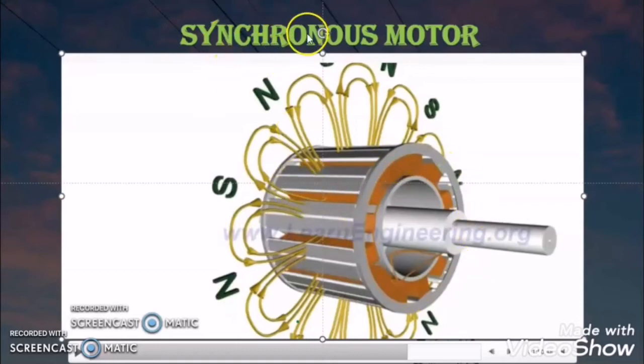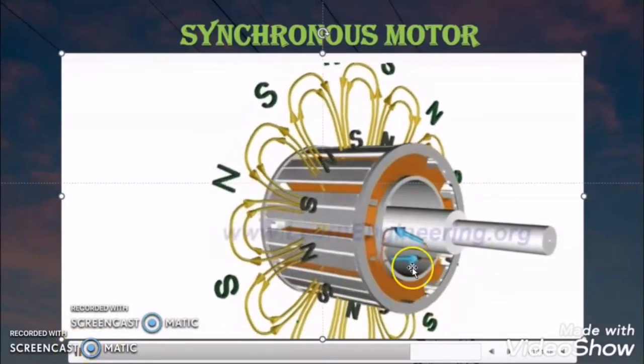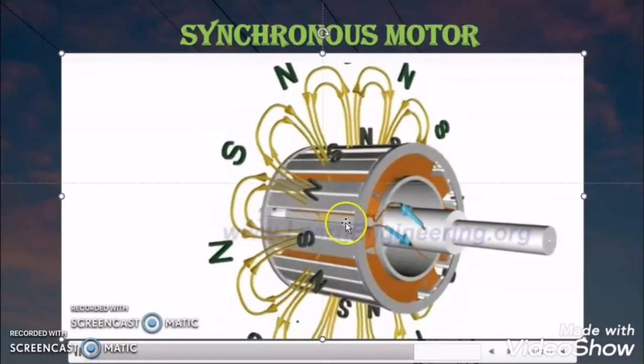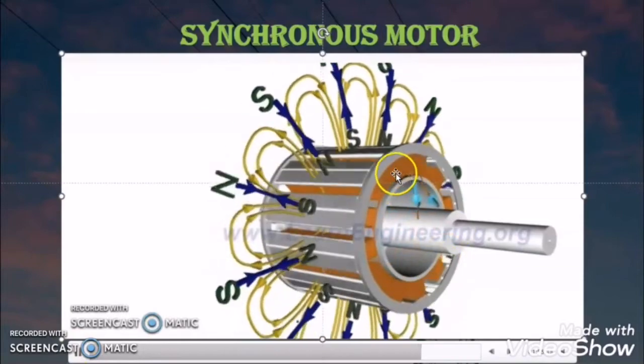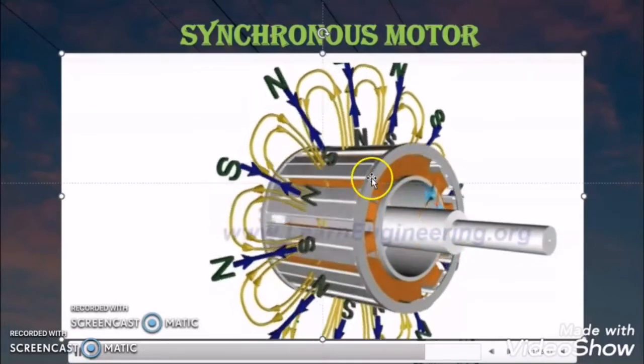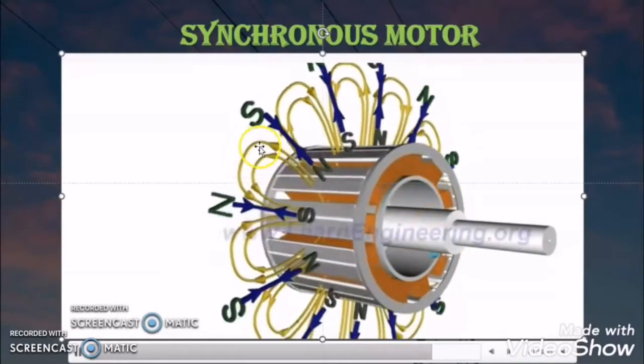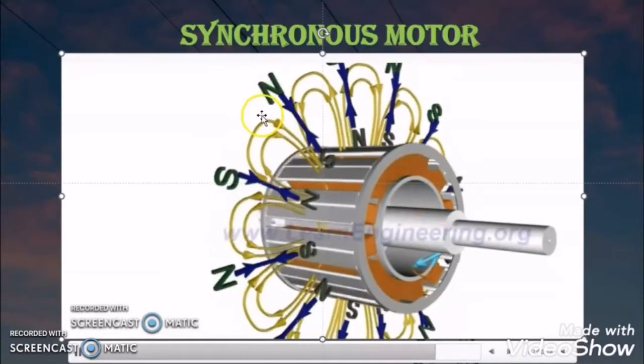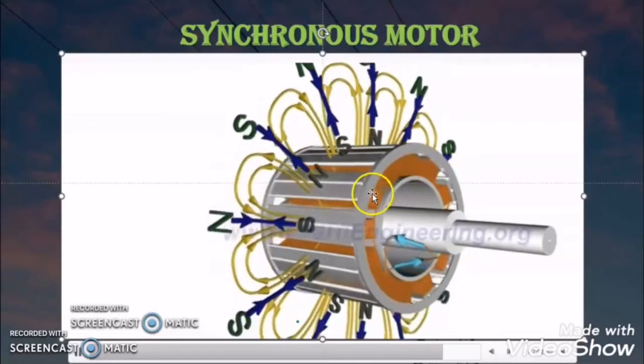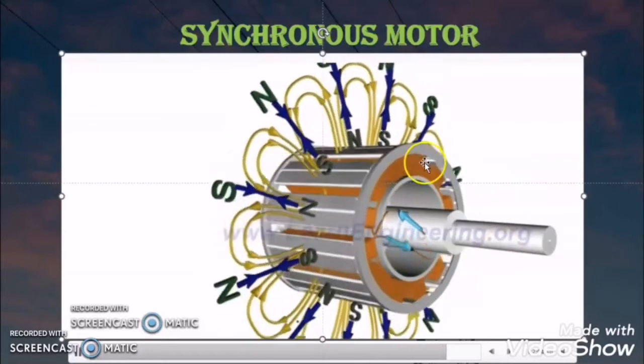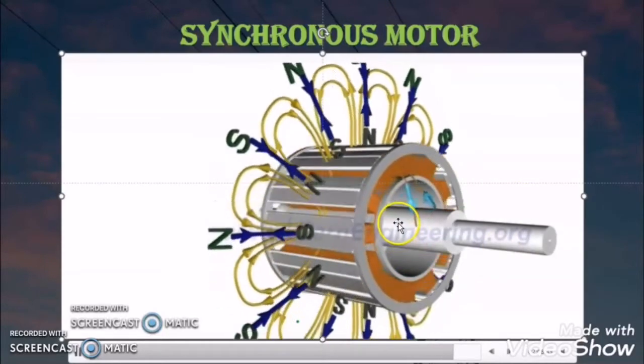With the help of this damper winding, we make the synchronous motor act like an induction motor at the time of starting. When we give power supply to the rotor winding of the synchronous motor, the rotor will rotate with the synchronous speed due to magnetic locking, and the damper winding becomes inactive.